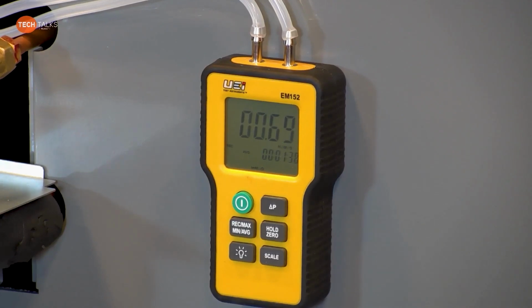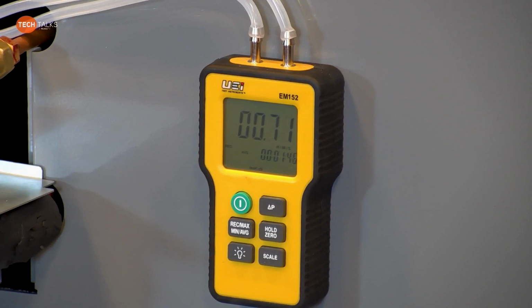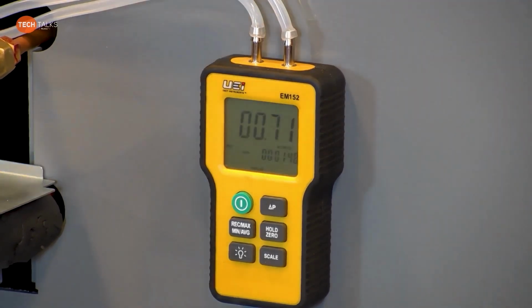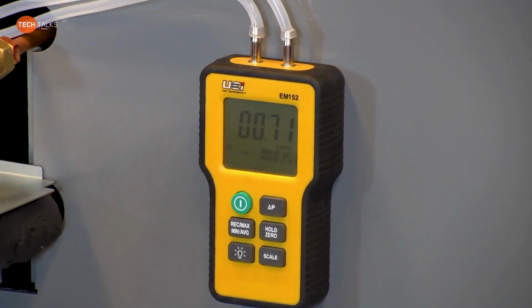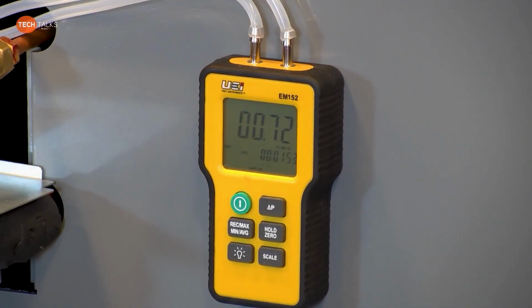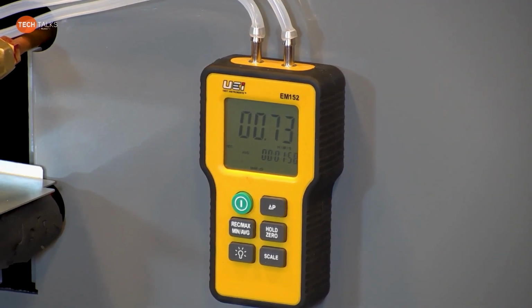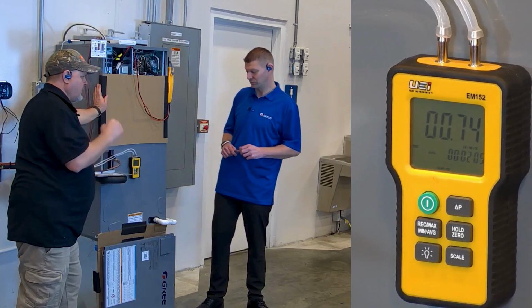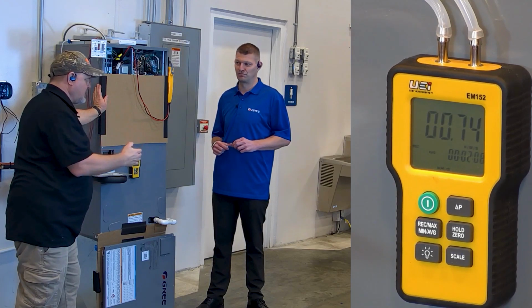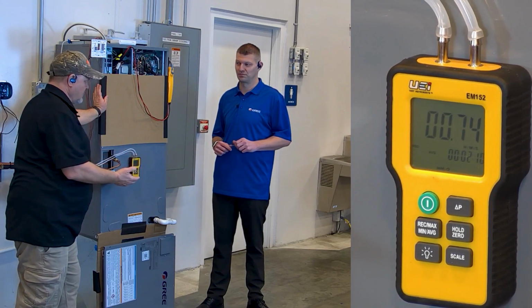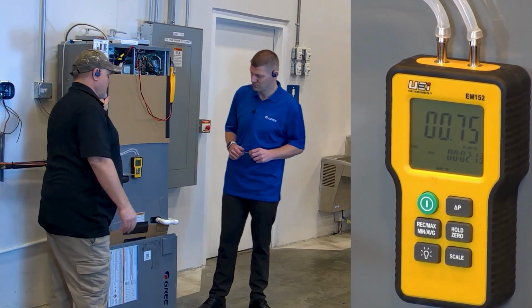If you start out where you're at 0.5 static and you're set to speed 3 and you're only moving 1,000 CFM, and you crank that thing all the way up to speed 5 and you're supposed to be going from 1,000 to 1,600, throwing an extra 600 CFM into ductwork that couldn't even move 1,000, you have no choice but that static pressure to go up. Even though the blower is thumping a little harder to try and overcome it, it's still not going to do it. So my explanation here is, do not assume that just changing the blower speed to a higher speed is going to force that unit to deliver the air that you need it to deliver. You have to do a static pressure measurement to verify that.